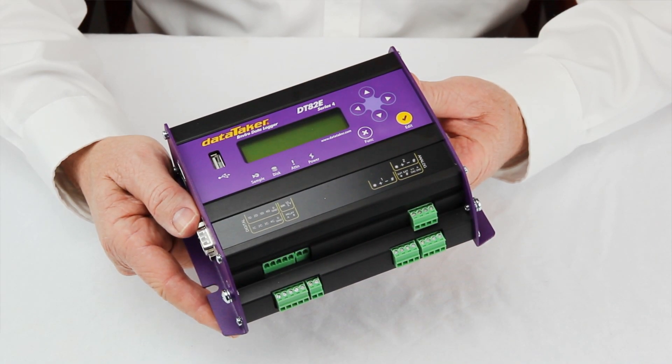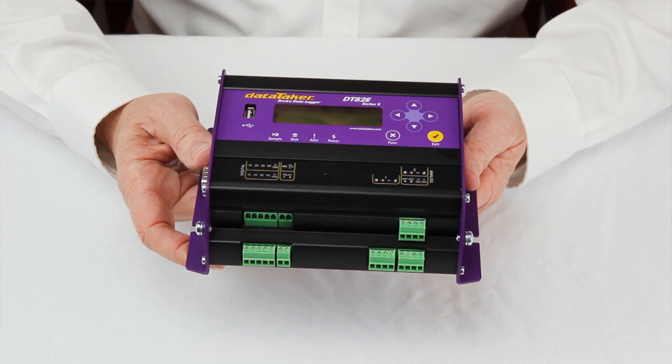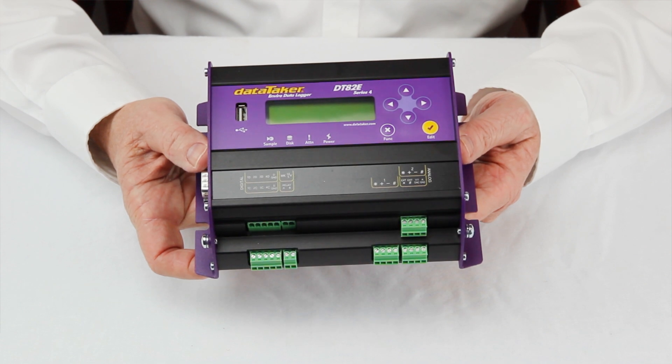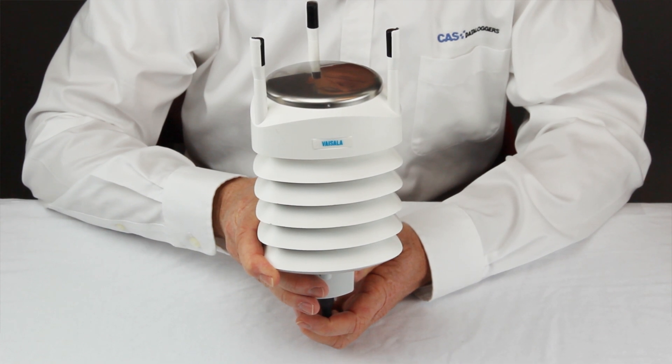The DT82E is a low-power universal input data logger that is designed to meet the needs of many environmental applications. In addition to two analog input channels that support most common sensor types, it has an SDI-12 communications interface for connection to smart sensors. For this demonstration, we are using a Vaisala WXT520 weather transmitter that allows the measurement of up to six different weather parameters in one compact package.